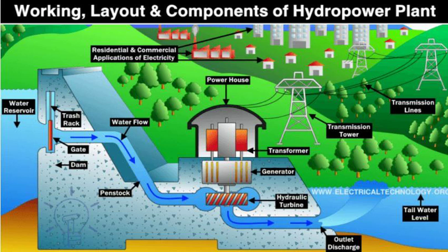generation unit. Forebay. A forebay or head pond is the temporary water storage, regulating reservoir provided at the downstream end of the canal just upstream of the penstock. When the turbine rejects the load, the forebay acts as a storage reservoir, whereas it supplies water, a sort of regulating reservoir, when load increases.